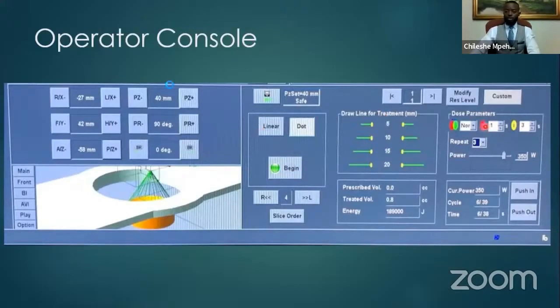On the right, we've got our dose parameter control system. This allows us to tell the machine how much energy to give, as in how much power it should be emitting. You can see this picture was taken while I was performing a treatment emitting 350 watts. I was just coming off a test dose, going up towards the maximum treatment dose of 400 watts, which is what we aim for.